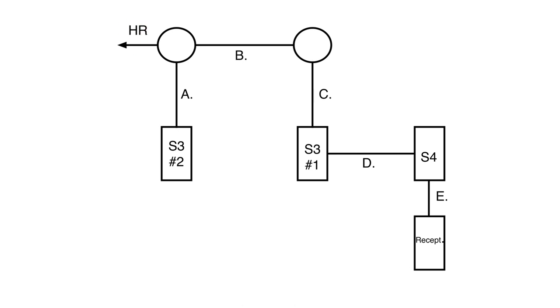This is not a very practical circuit — you would probably not lay out your circuit like this at all. But let's just say somebody went ahead and ran pipe from this three-way switch up to that light, between the two lights, down to the other three-way switch, into the four-way switch, and down to the receptacle. It's up to us to determine how many wires are going into each pipe.